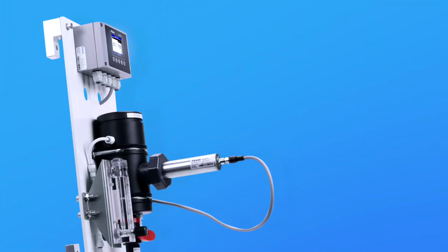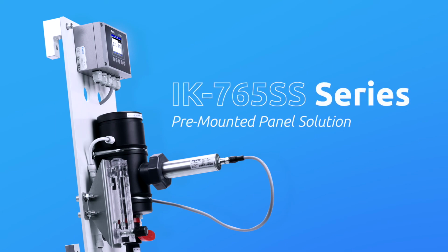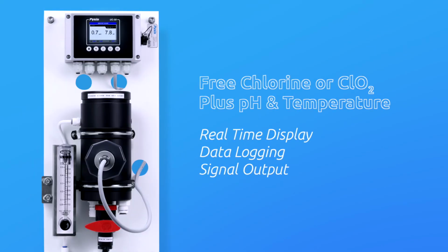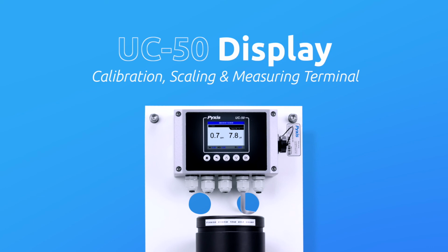For those desiring a turnkey solution, Pyxis Lab offers the newly released IK765SS series panel platform. The IK765SS series is a pre-assembled free chlorine or chlorine dioxide, pH, and temperature monitoring panel consisting of the ST765SS series sensor, selected with a pre-mounted FR50 flow reservoir, and the UC50 display and data logging terminal. These platform solutions offer real-time display, data logging, and signal output capability of sample free chlorine or chlorine dioxide, pH, and temperature. The UC50 is a microprocessor display data logging terminal that has been pre-configured to connect Pyxis inline sensors with fully integrated calibration, scaling, and measurement protocol.